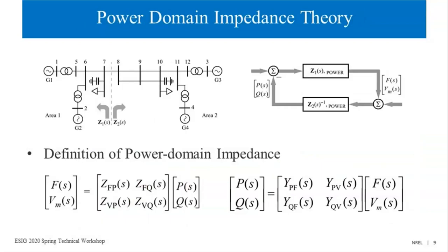To really understand how we analyze this kind of oscillation, we are defining impedance in a slightly different way, what we call power domain impedance, where instead of relating voltage to current, the transfer functions are from active and reactive power to frequency and voltage magnitude. We can use these transfer functions to understand low-frequency active and reactive power oscillations in inverter-based resources.